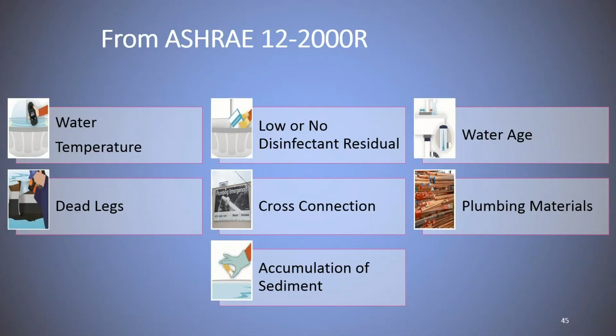If we take a deeper dive into ASHRAE 12, there's criteria for management of identified risks. Attention must be paid to water temperature, dead legs, cross connections, water age—things we think about, but now that we know about water, we must act on it. Action is key to remediate systems when you identify any of these risks outlined in ASHRAE 12.